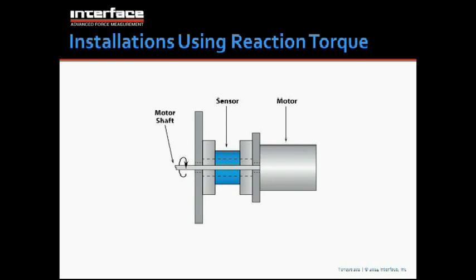To alleviate that, the motor could be supported, say, on bearings or some way to keep it from applying too much load to the sensor in a bending orientation. But this is a pretty good installation. In some cases, the trick is you have to be able to mount your motor to the reaction sensor, and you have to be able to mount the reaction sensor to whatever it is that you need to mount the motor to, basically, and that can require adapter plates or whatnot, and certain motors lend themselves to that more than others.